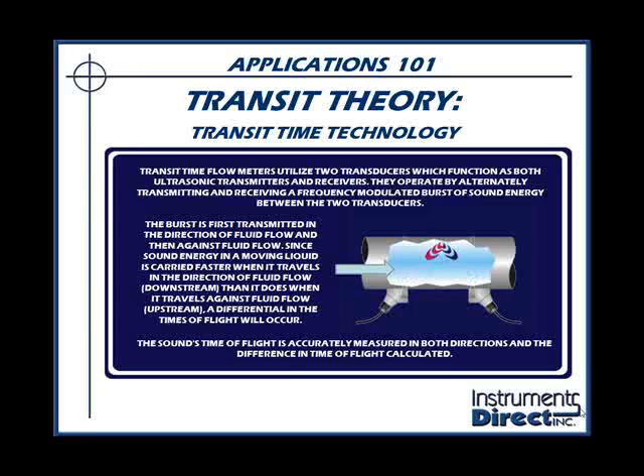In the picture to the right, we have two ultrasonic transit time transducers strapped to a pipe. They are installed in what's called the V configuration, where they're both on the same side of the pipe. This is the most common installation for this type of technology. The transducer on the left will send out a sound beam burst across the pipe, reflect off the back wall, and be received by the transducer downstream.